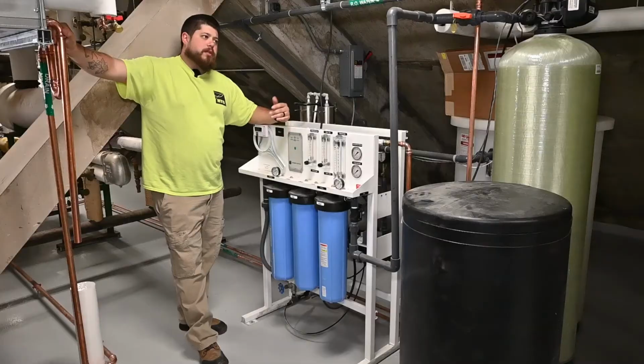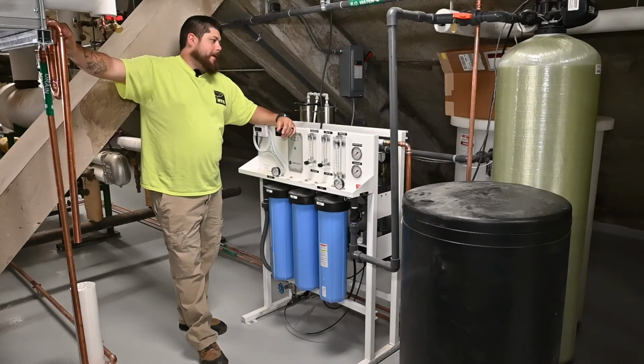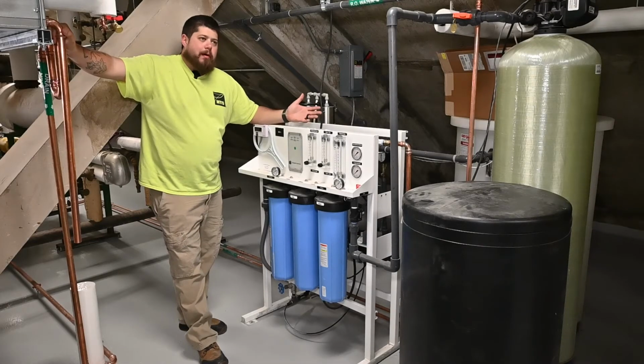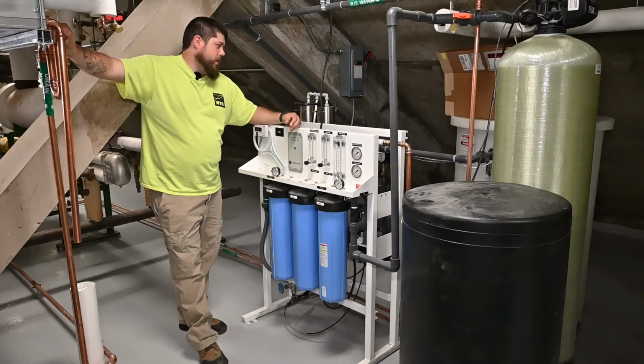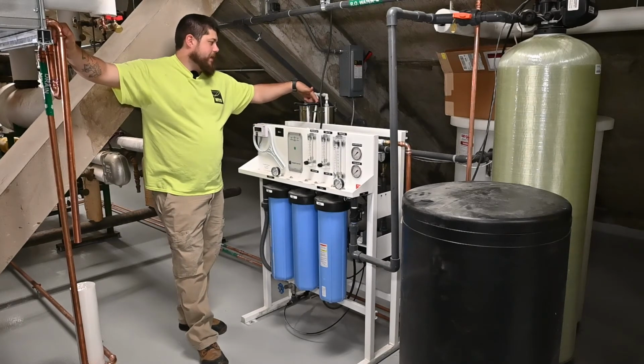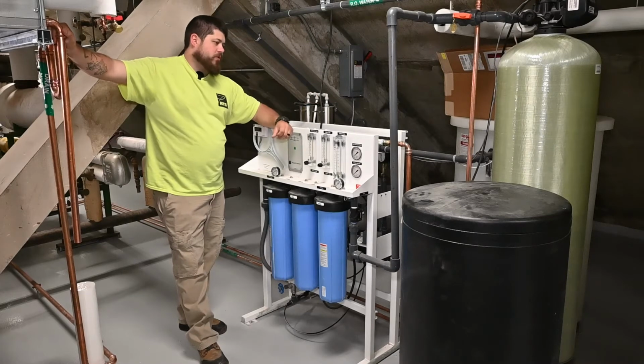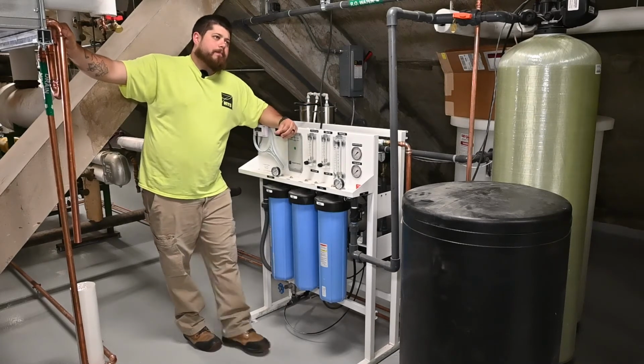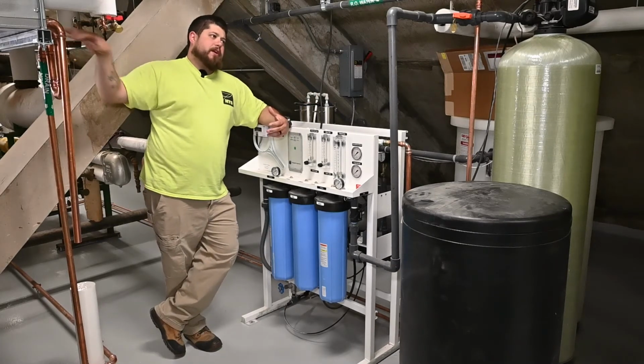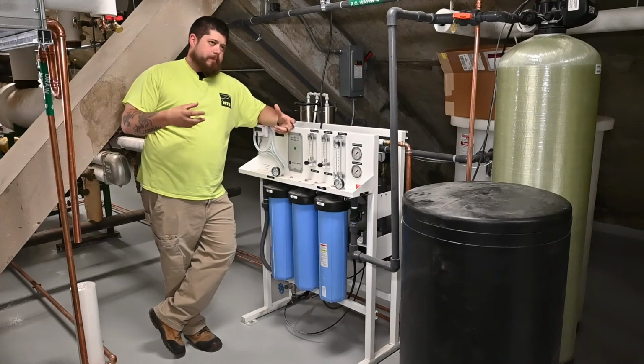While you're doing that, you're going to lose your DP across the pump, which is going to let it drain. It's not something that should ever really happen, but for any reason that it does occur, that's the easiest way to do it. There are 2 membranes inside of these canisters right here. Those shouldn't have to get messed with. If they do get replaced, they're going to come with 2 O-rings.